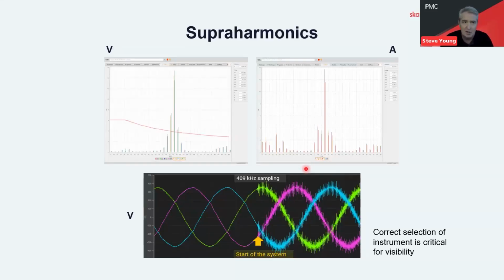The top left-hand image shows the information from the instrument with respect to voltage. The red line indicates the limit by way of IEC 61000-2-4 class 1, and we can see a significant exceedance in that value, and that indicates the switching frequency of the inverter. Now, that's going to have one phenomenon that we call constant high frequency voltage disturbances. But as we draw current at that frequency on the right-hand side, we're going to see corresponding current drawn at that dominant frequency. And that has its own set of considerations that we can now take a quick look at.